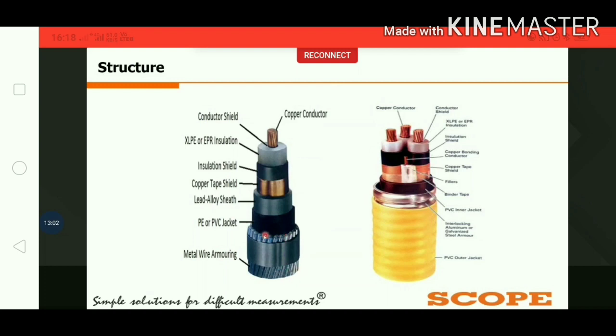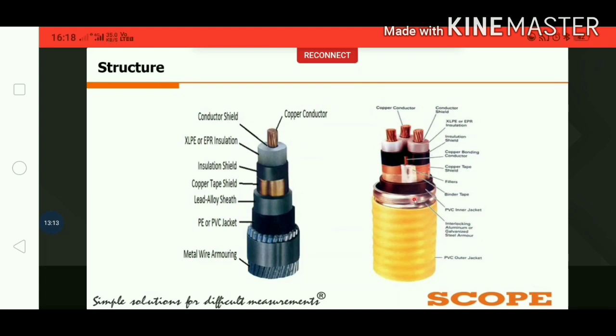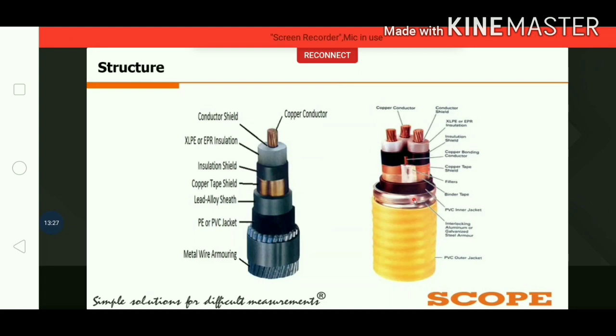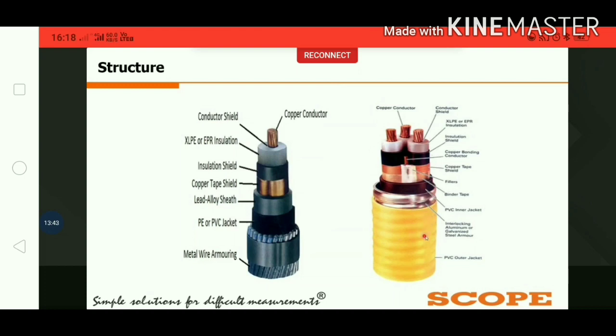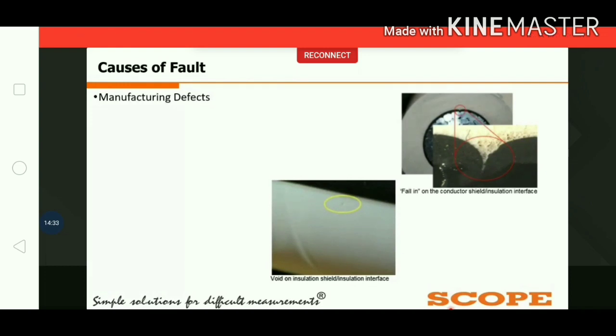Cable armor is mainly used to provide mechanical protection. Steel wire or aluminium wire are used for armoring, with a galvanizing process applied to provide rust protection. However, steel is magnetic in nature, so when electrical current passes through the cable, eddy currents develop in the steel material causing overheating. That is why aluminium armoring is widely preferred in the industry. The outer PVC jacket provides mechanical, chemical, and electrical protection to the cable.